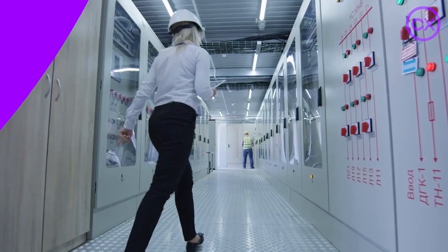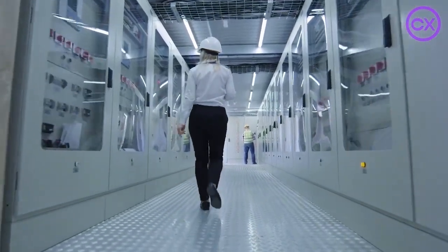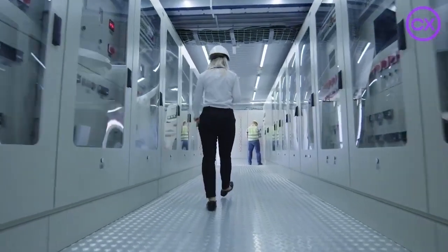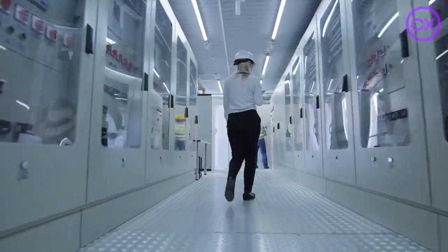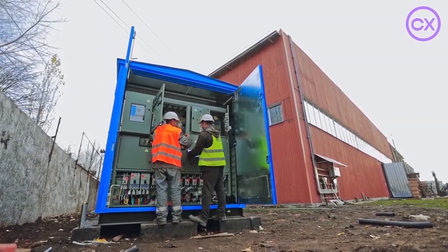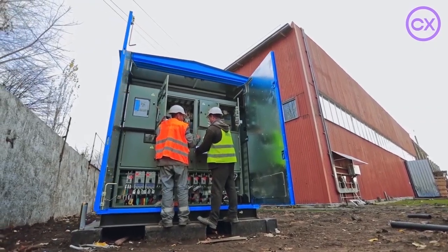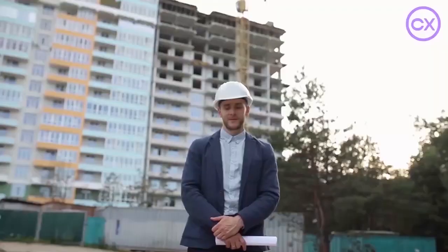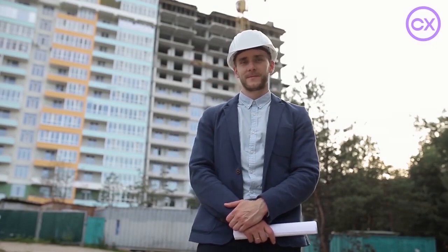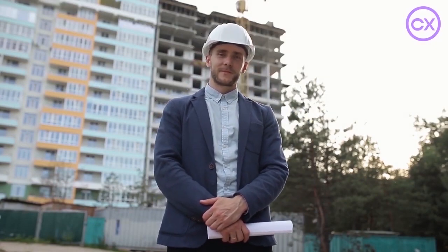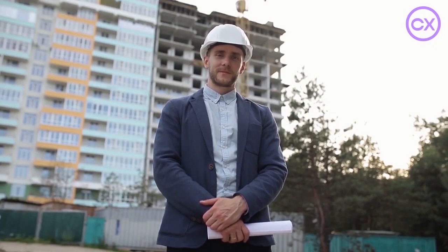An example of an electrical pre-commissioning checklist is energizing an automation cubicle for the first time. In this checklist, it would contain basic communication checks, alarm and set point checks, control and monitoring checks, loop checks, and much more. Once all pre-commissioning inspections are complete, the systems can then be further tested during commissioning testing.